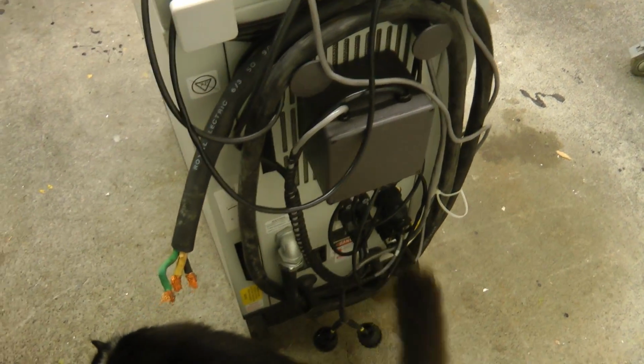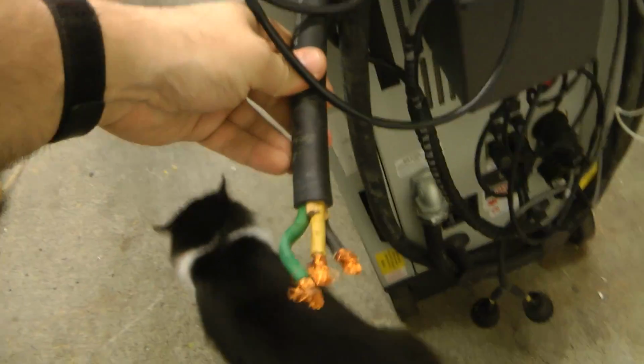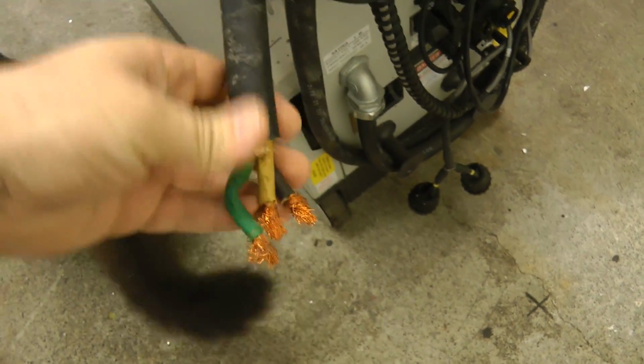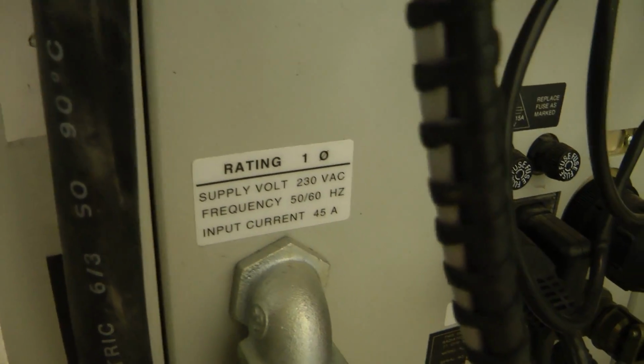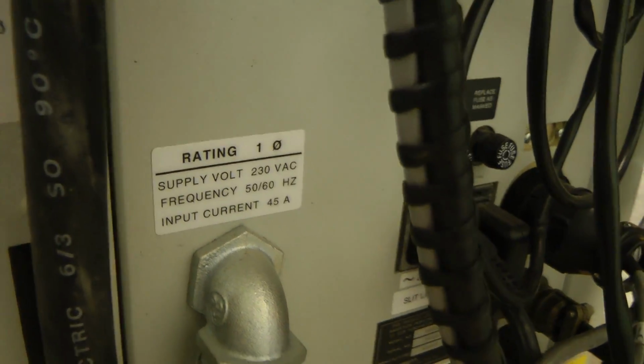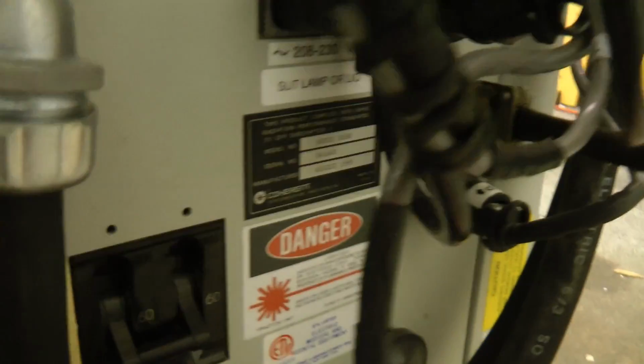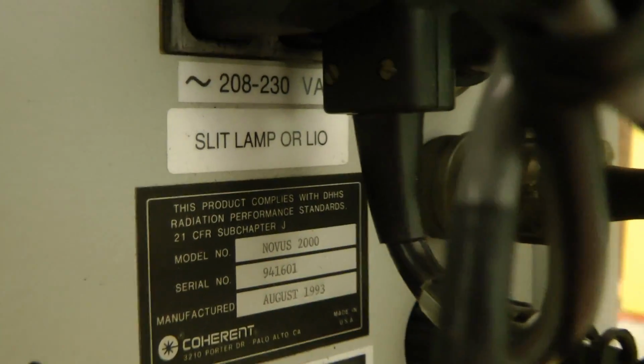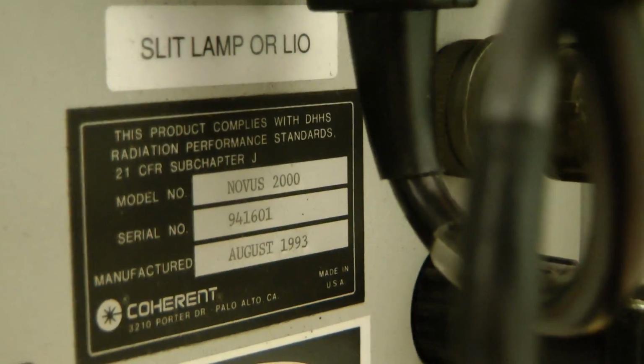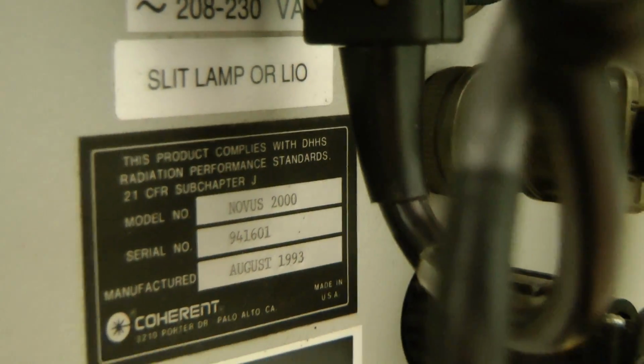And since the low efficiency of argon lasers, it takes a lot of power, as you can judge by the power cord, 6 gauge. Input rating is 230 volts at 45 amps. According to them, this is a Novus 2000, made in August 1993. We'll have to see if this thing actually works or not.